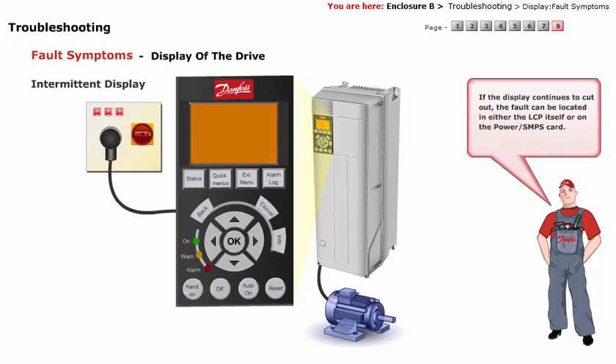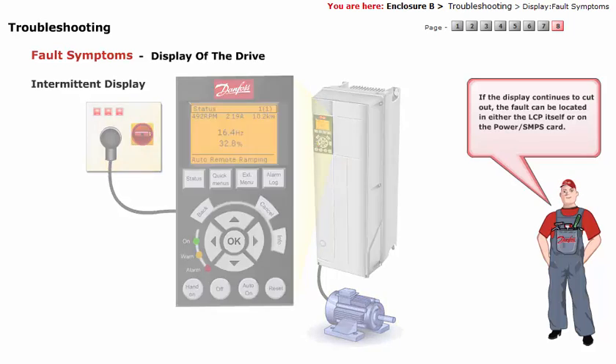If the display continues to cut out, the fault can be located in either the LCP itself or on the power or SMPS card.